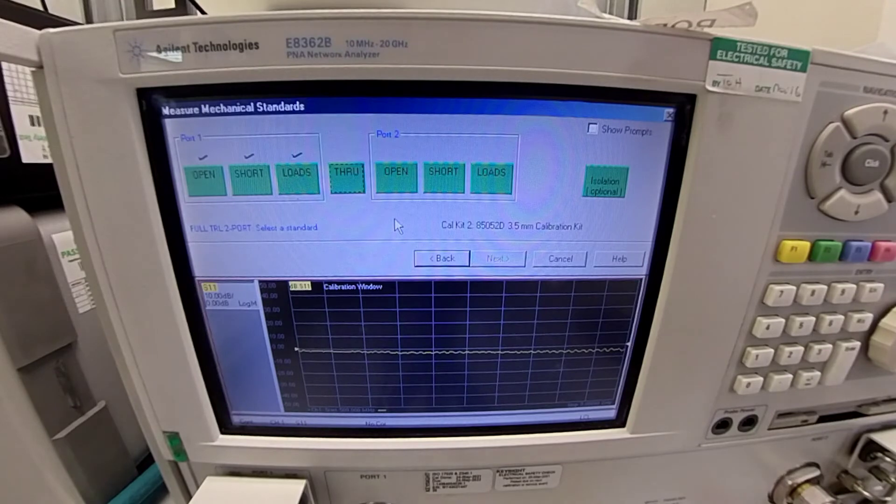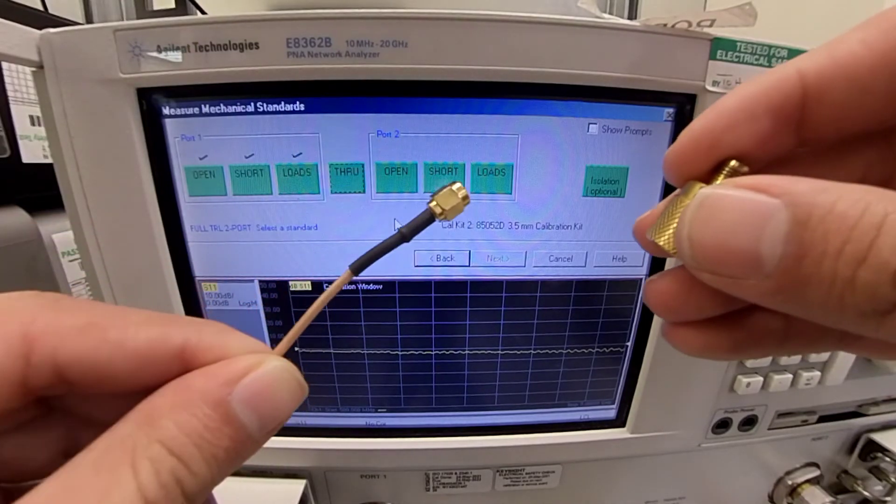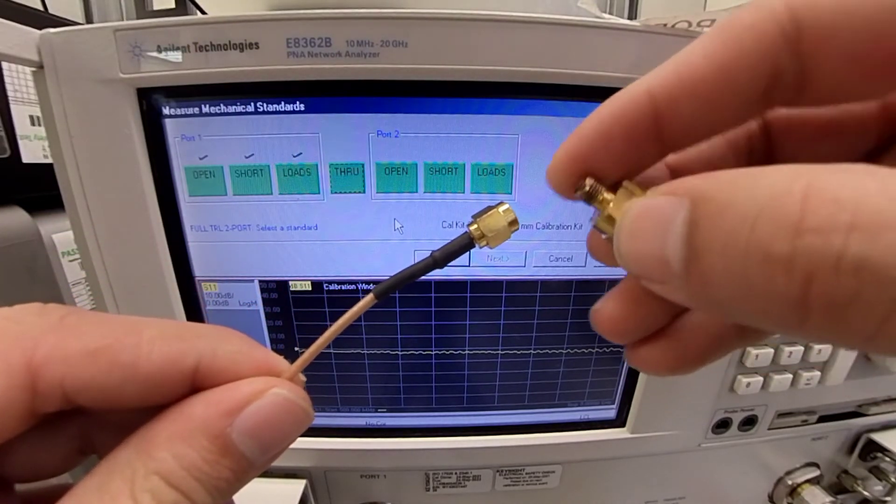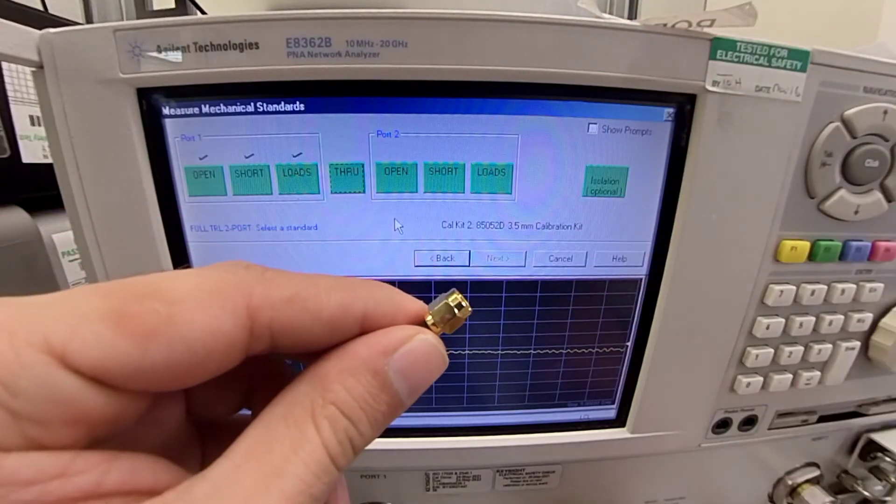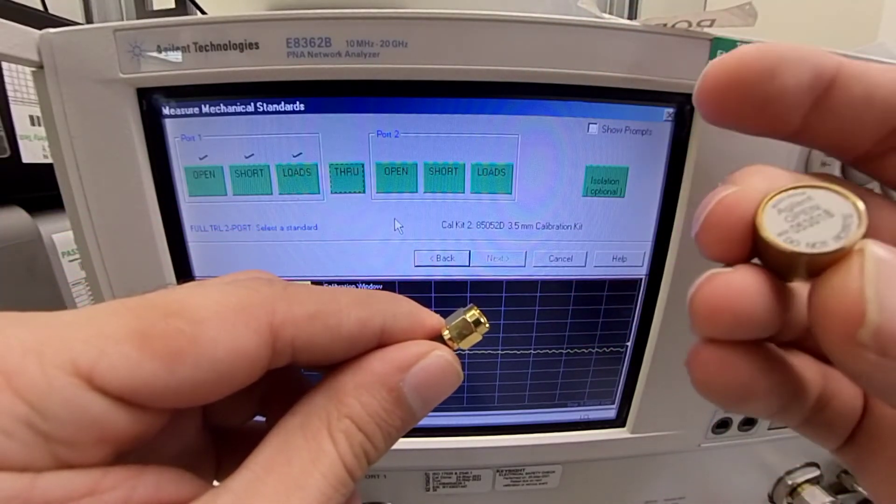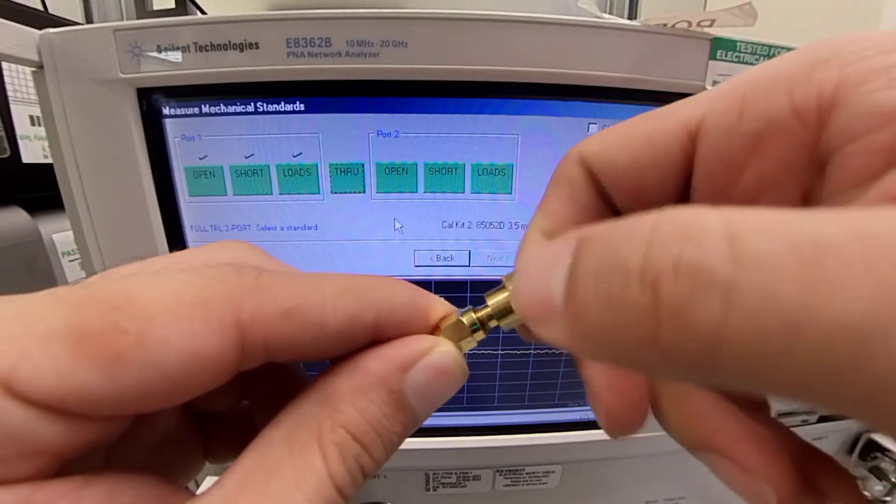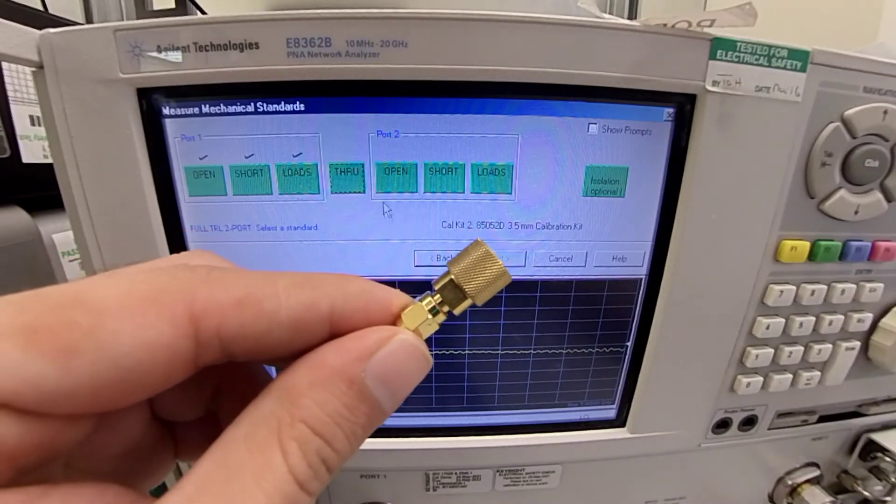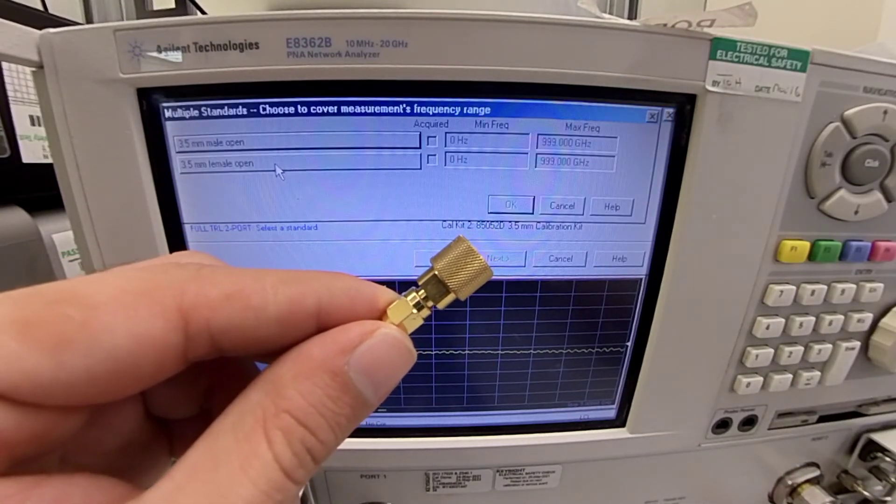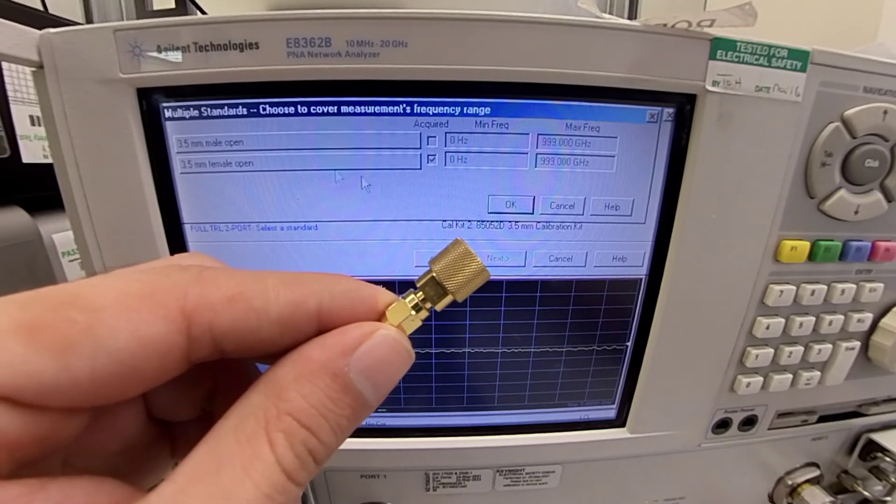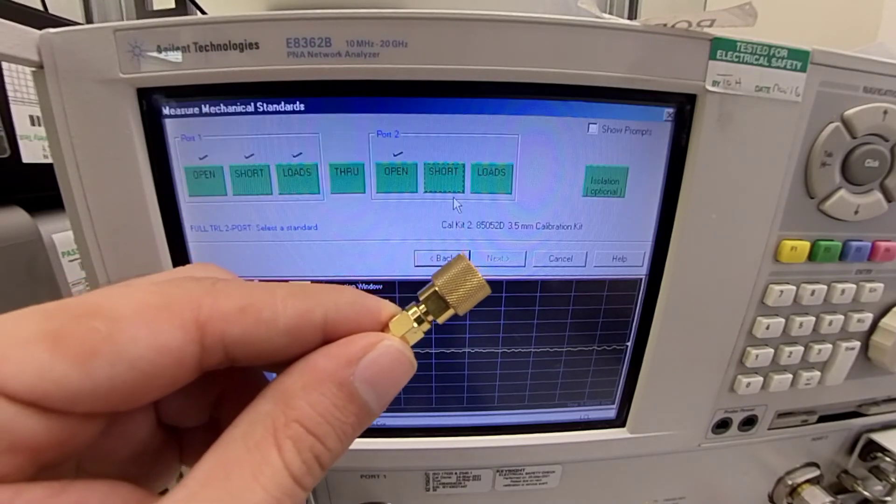For the second port, we select the cable connected to the second port, which is the brown cable in this video. And we start off again with an open circuit load. We select Open. Repeat the same procedure. Female, open. Press OK. And we are done with the open circuit.